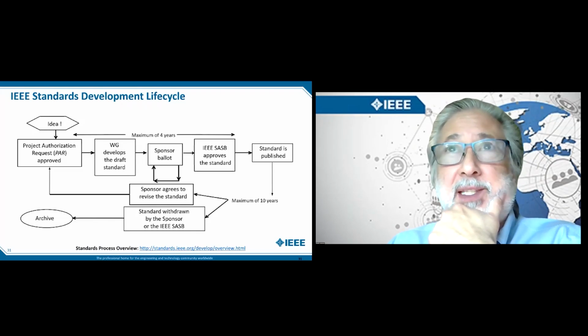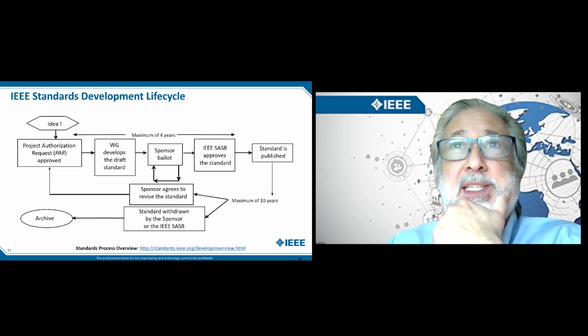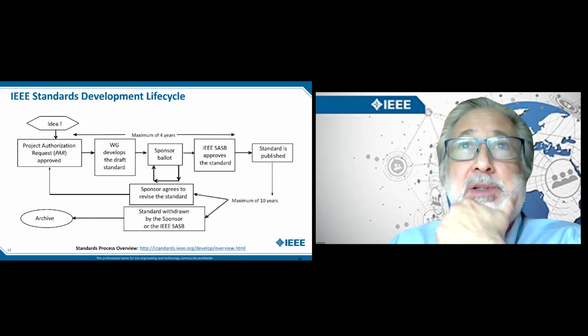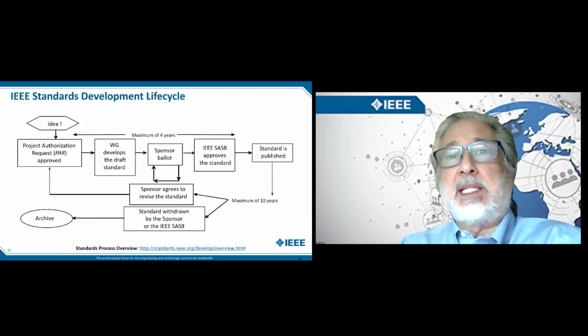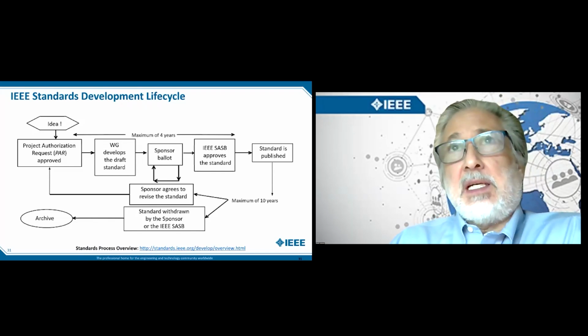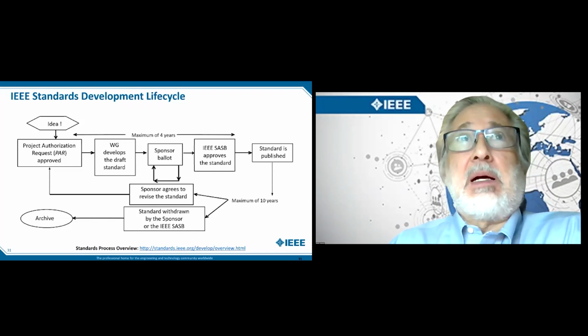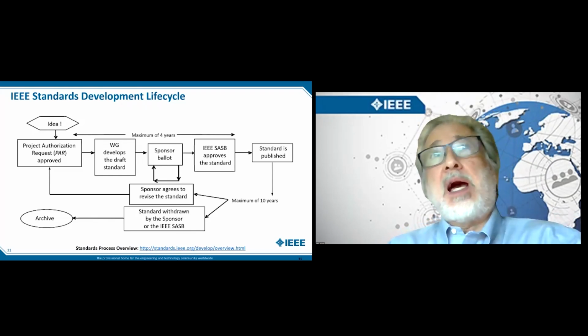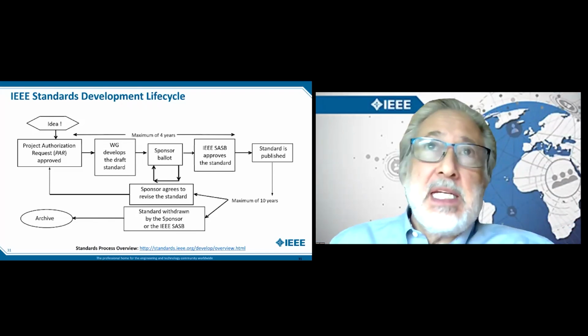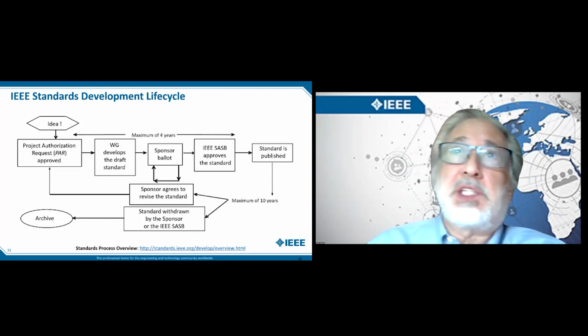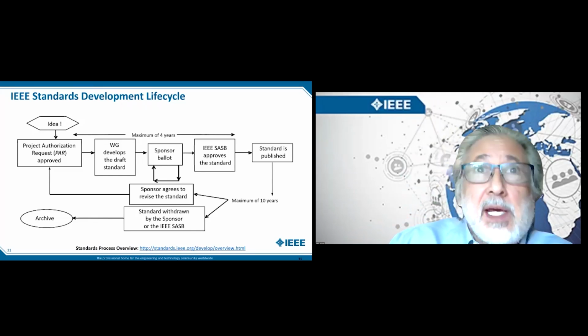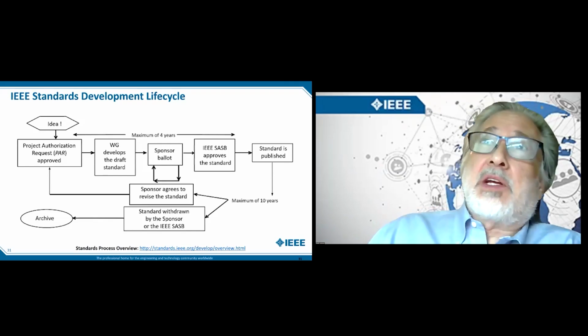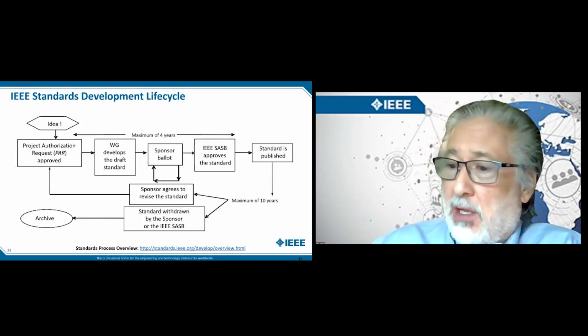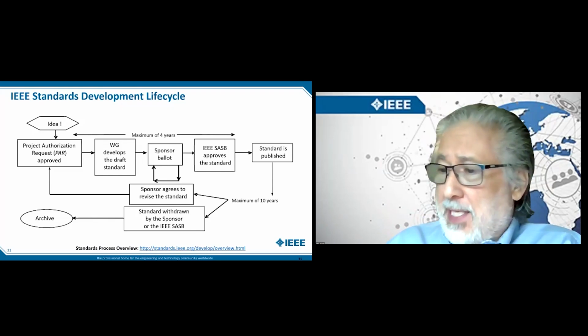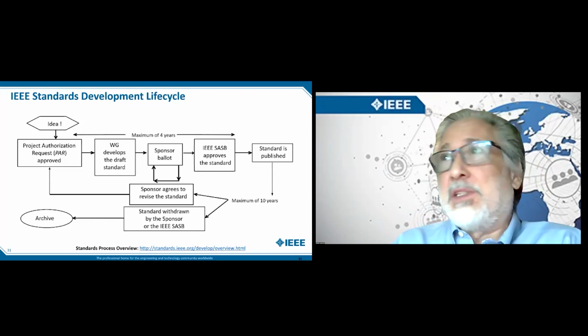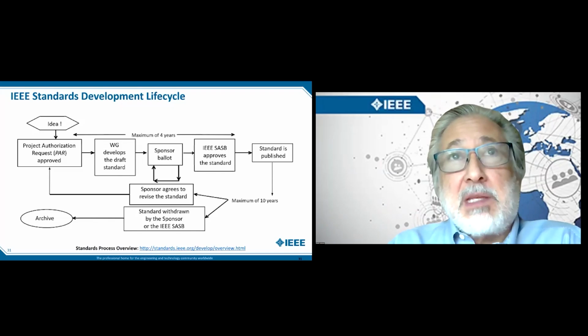Mark had said the IEEE requirement is 10 years. It took longer than that to revise 1547 from 2003 to 2018, but the goal is to get this renewal cycle down to 4 years or less, mainly because the technology and how distributed resource technology is used is rapidly changing. The pace of change in technology and its use on the grid is ahead of that 10-year cycle, and I'd say 4 years is even pretty long, especially at the moment.